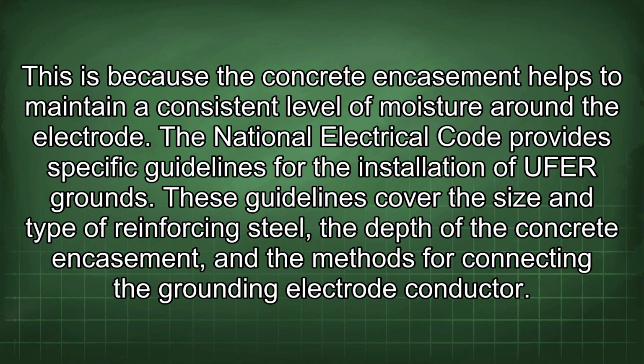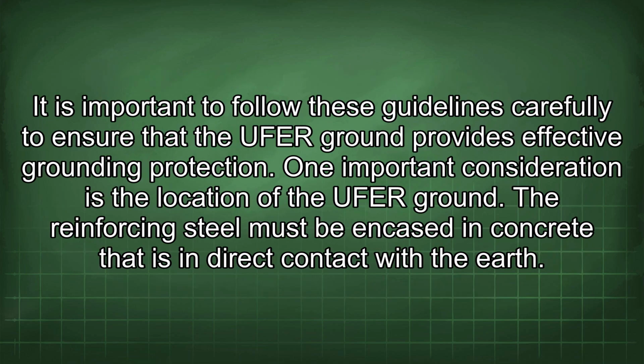The National Electrical Code provides specific guidelines for the installation of UFER grounds. These guidelines cover the size and type of reinforcing steel, the depth of the concrete encasement, and the methods for connecting the grounding electrode conductor. It is important to follow these guidelines carefully to ensure that the UFER ground provides effective grounding protection.